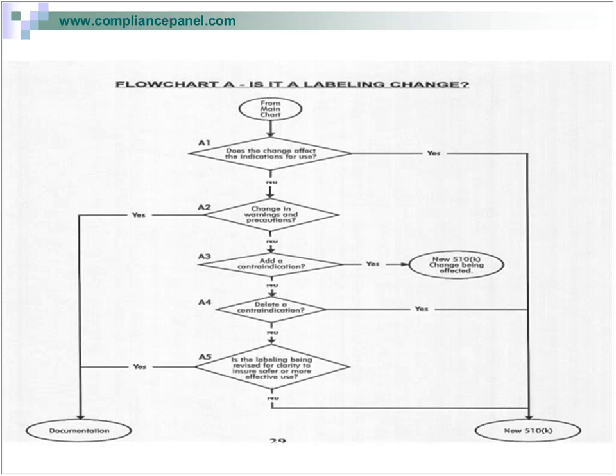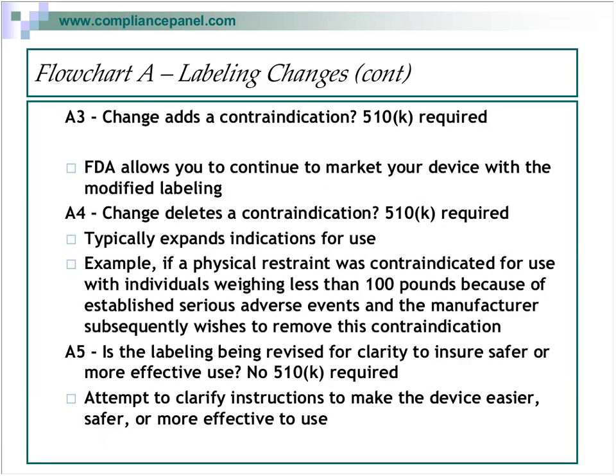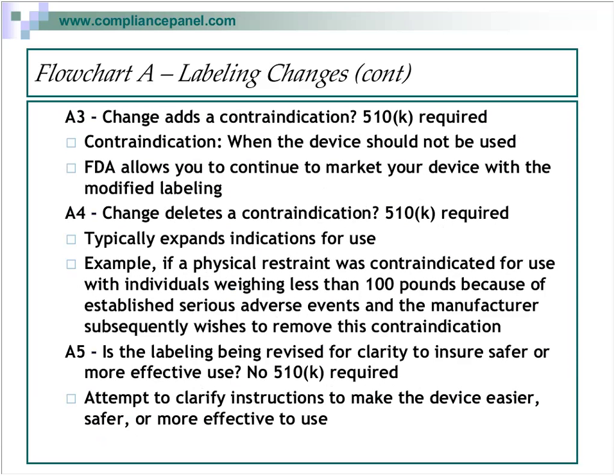A4, if you're going to delete a contraindication, what this does is, when you delete a contraindication, this shouldn't be used in the following circumstance. That's a contraindication. What this does is it expands the indications for use. An example that I've seen in the literature is if a physical restraint that you sell was contraindicated for use for people weighing less than 100 pounds because it might not hold them, and you're going to remove that contraindication, now you're expanding the indications for use. You need to submit a 510K for that particular device.